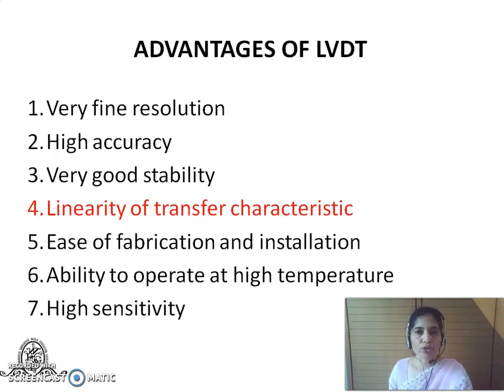Some of the advantages of LVDT: it has very fine resolution, it has good accuracy. The most important advantage is the linear characteristic between the output voltage, which is the differential voltage, and the core position. So the linearity of the characteristic is the most important advantage of LVDT. It also exhibits a high sensitivity, that is, a small change in the core position reflects in a good amount of change in the output voltage.